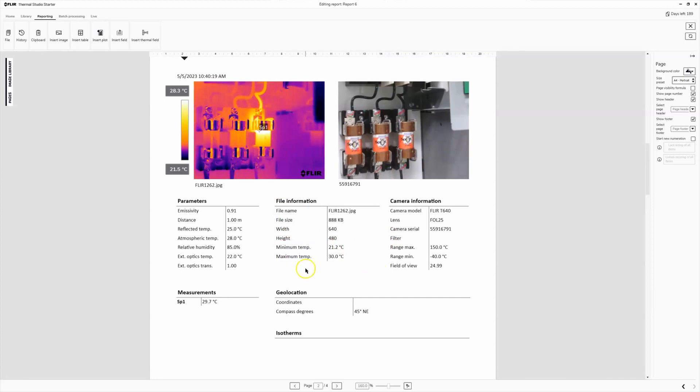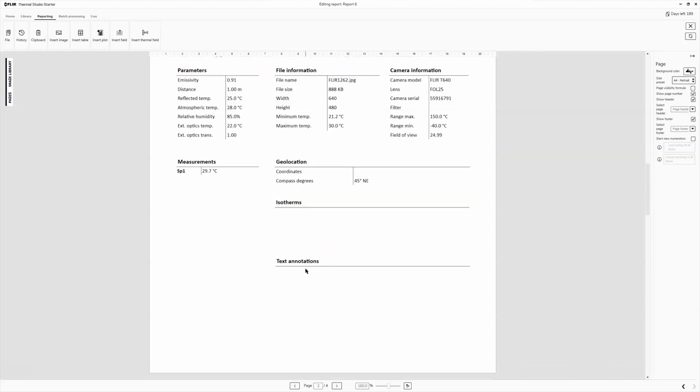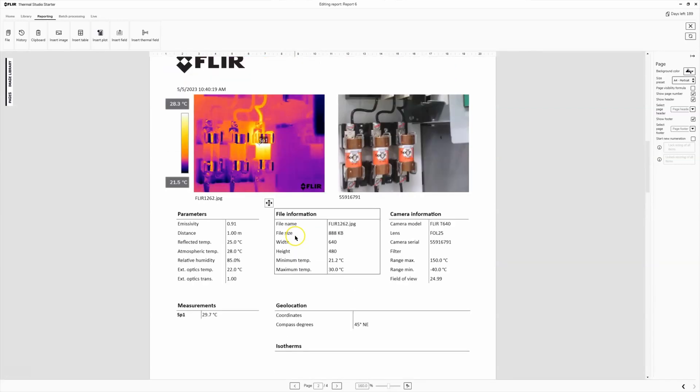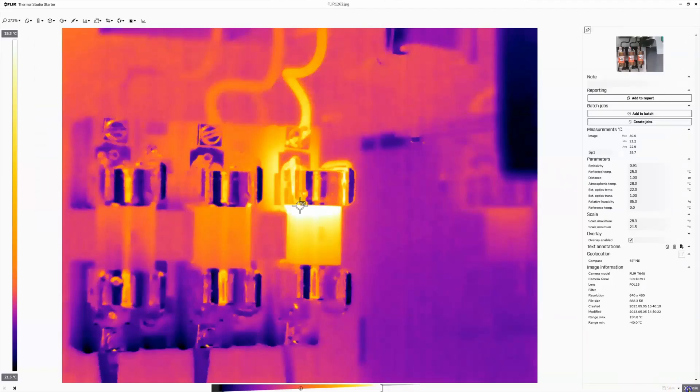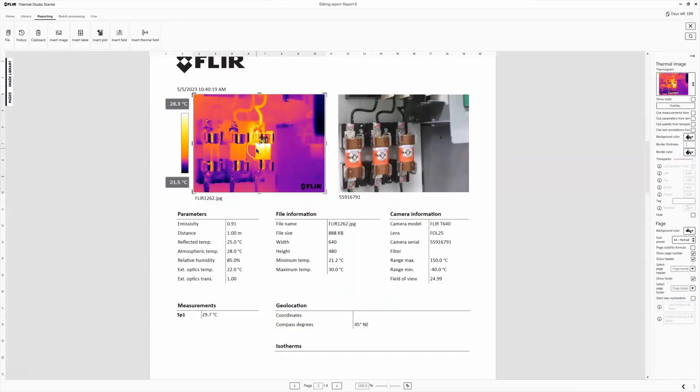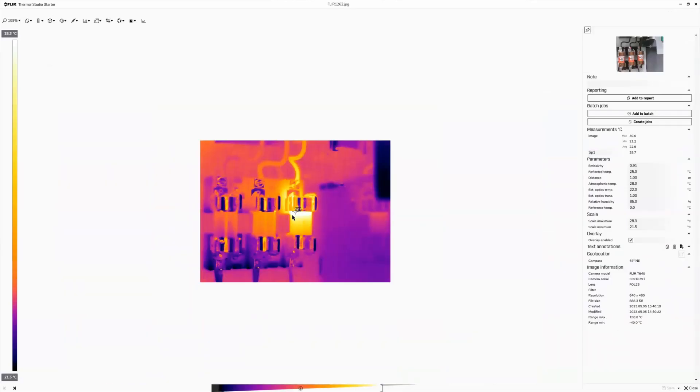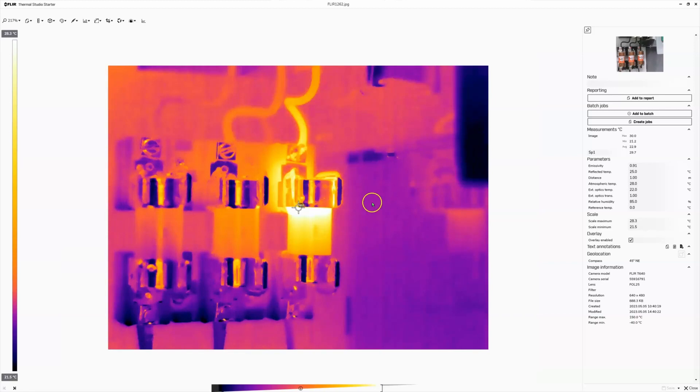So on here, we've got a couple of things that we could fill out. Really all I'm going to worry about is getting the most information out of this as I possibly can. But if I double click on the thermal image, it takes me to this really blown up version of it. And I've got a lot more information over here. So what I want to do in this case, this is a fuse holder that I saw one of the fuses was hot. So what we're going to do is we're going to change the spots on here. It's this one. So we're going to spot meter.